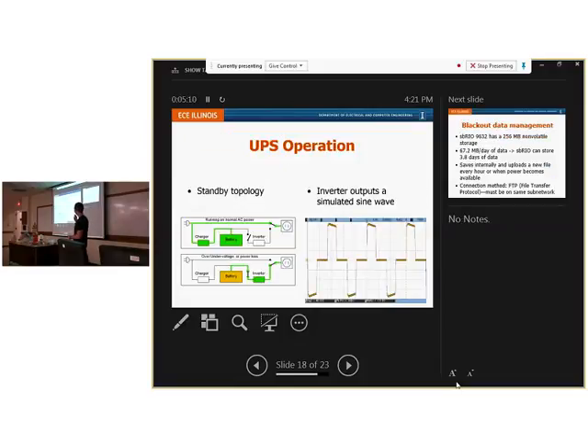This shows how the UPS operates. It works on a standby topology, which we later found out is not good for us because we don't want any switching involved. The switching comes from the fact that during normal operation, voltage is transferred directly from the grid to our power supply, which supplies our PMU. But during a blackout, switching occurs, getting power from the inverter or the battery through the inverter, and that switching is not good.